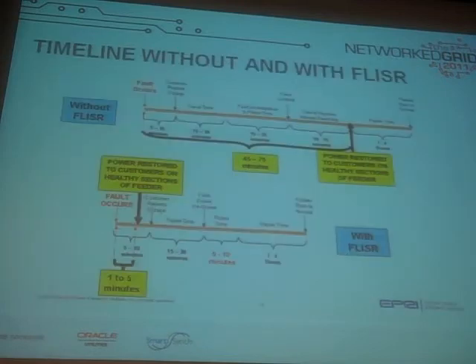This next slide shows a timeline without and with FLISR. Without FLISR, a fault occurs, 10 minutes go by before the customer calls the utility, then another 15 to 30 minutes to drive out and look for the fault, another 20 minutes to locate it, and another 20 minutes before the switch can be manually turned. So you're looking at 45 minutes to 2 hours before power is restored to the healthy customers.